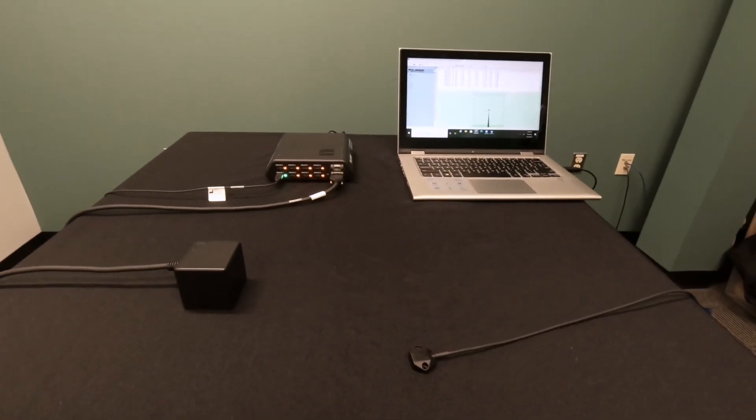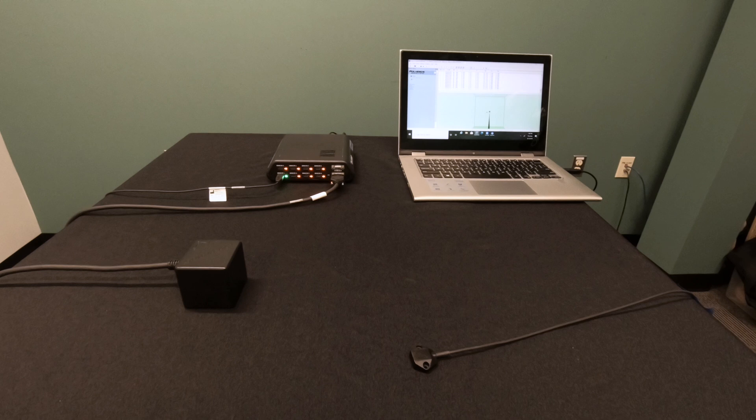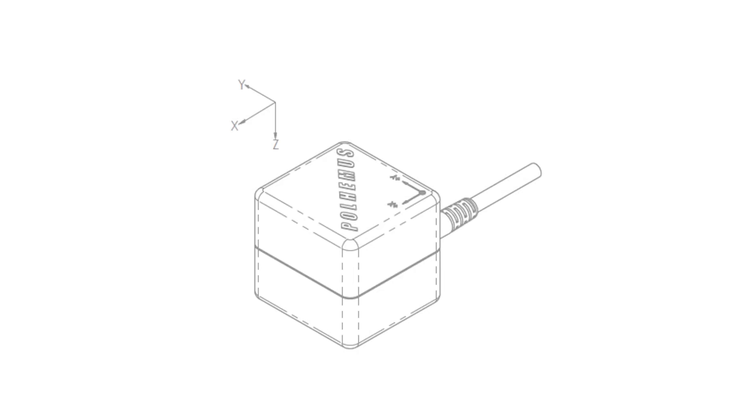Now that your source and sensor is connected to the system electronics unit, the sensor should be placed in front of the source in the positive x hemisphere. The positive x direction is clearly noted on top of the source.